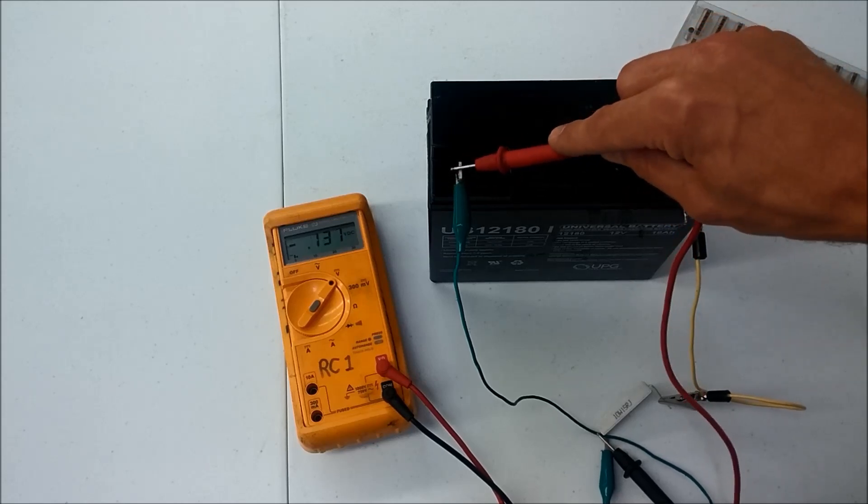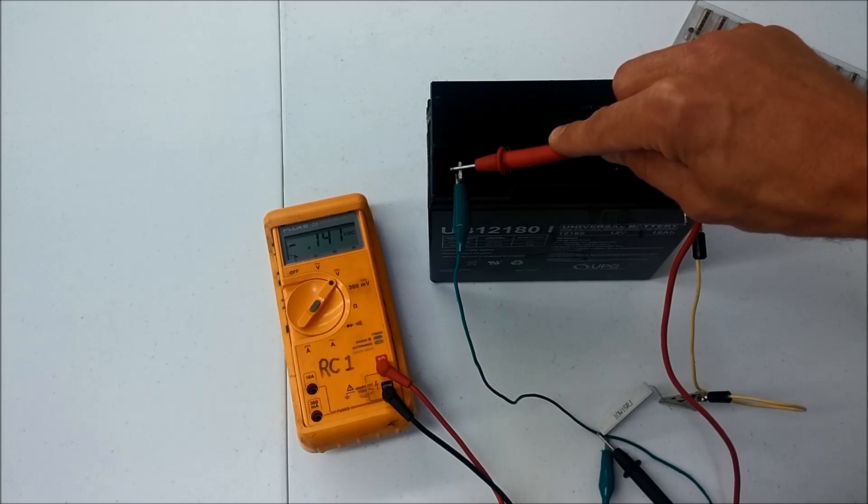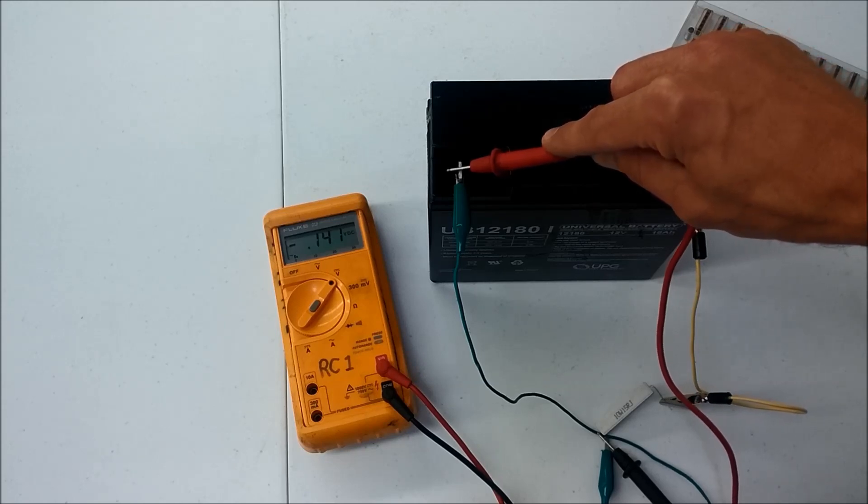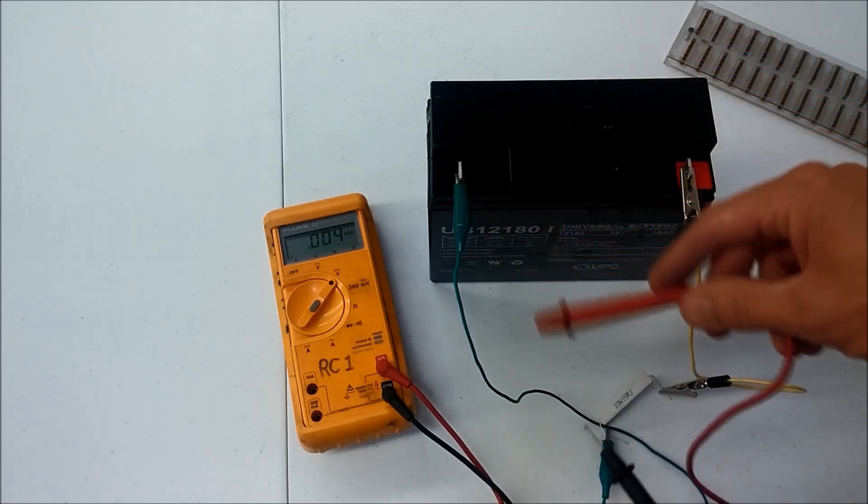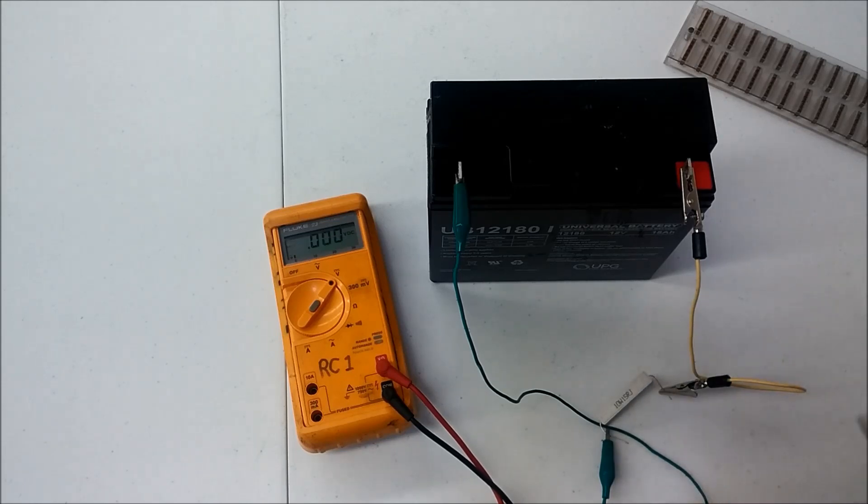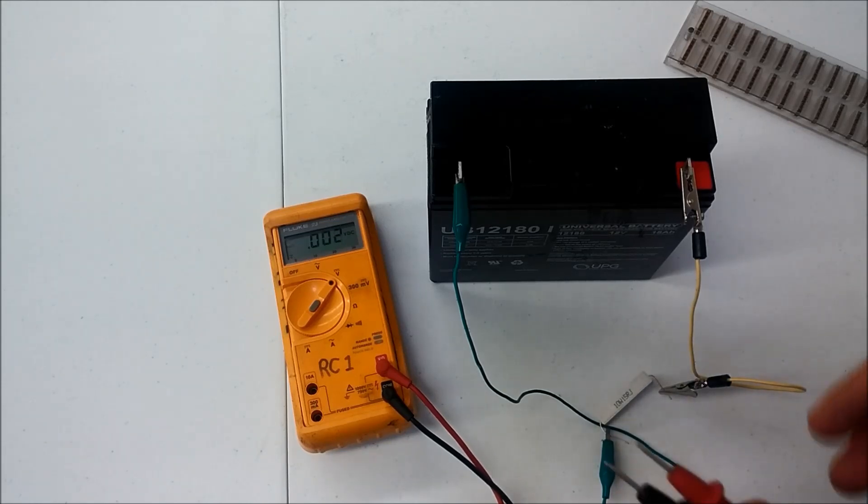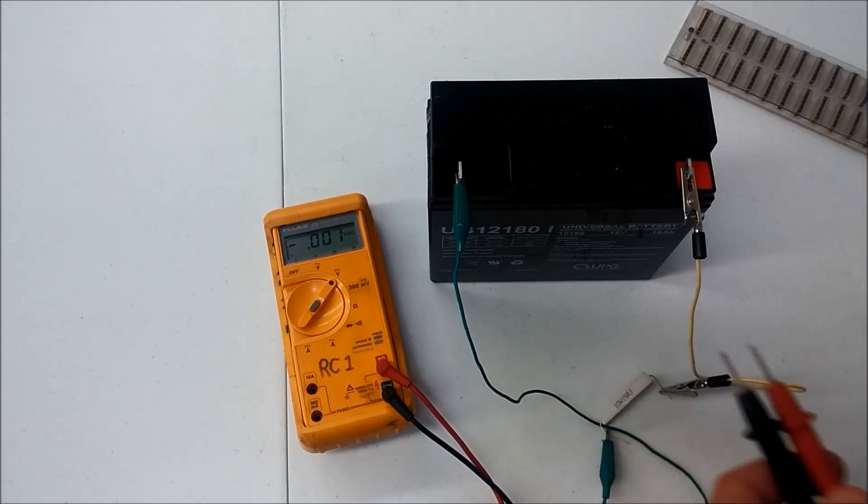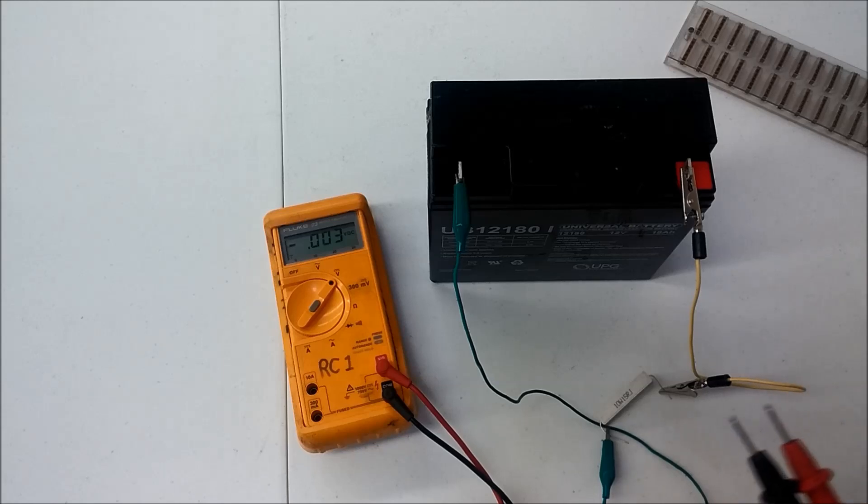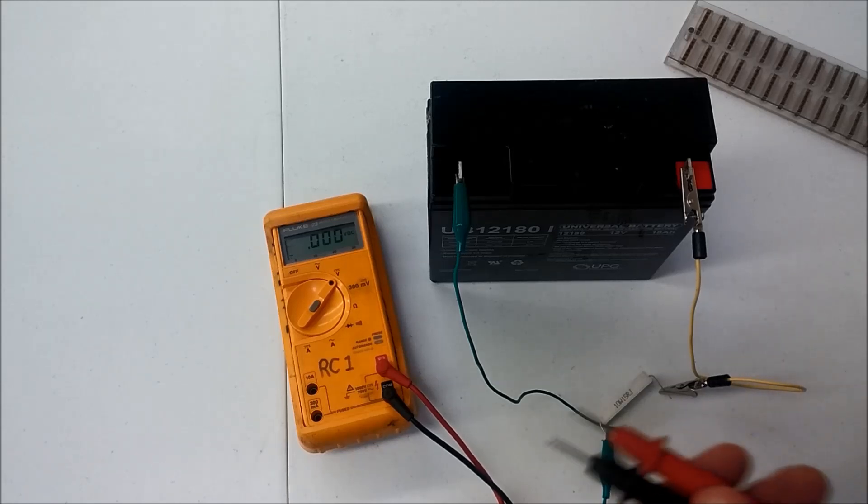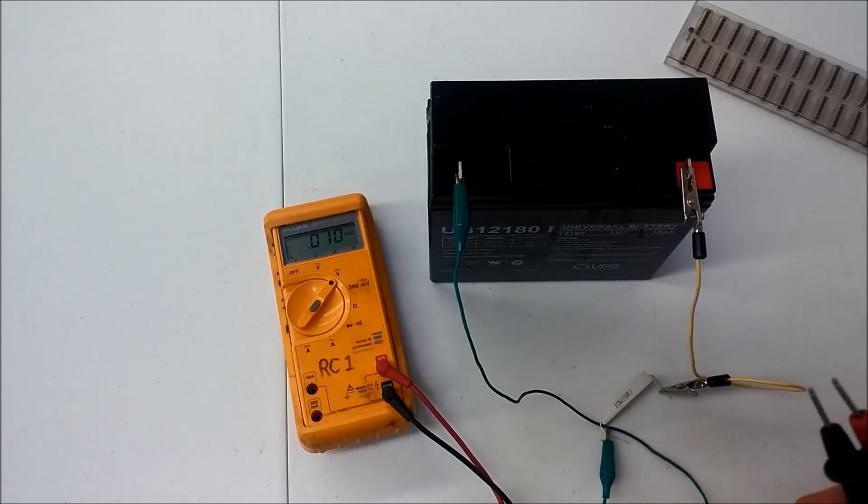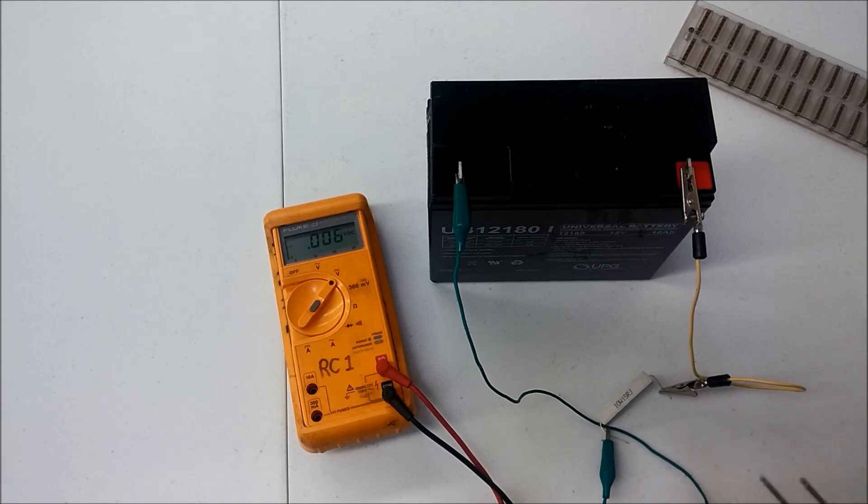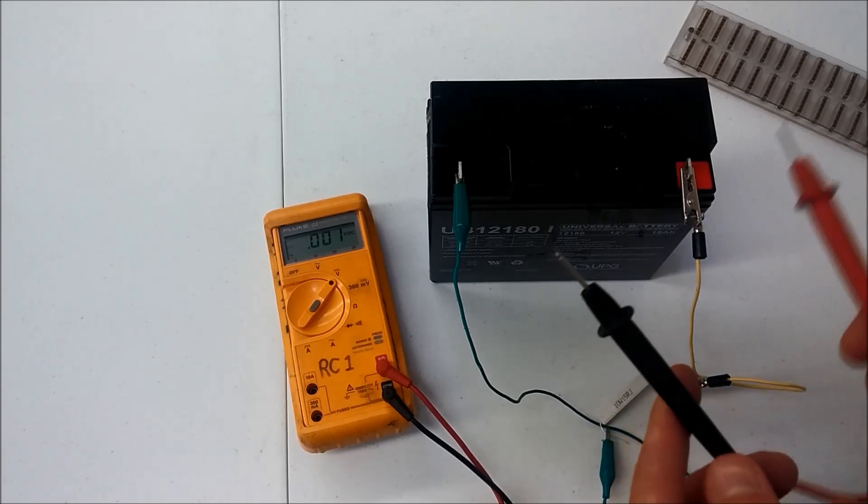Sure enough, it's close. About 0.14 volts difference from one end of the green wire to the other, so that green wire is actually causing a small voltage loss, but it's not a lot. It'd be similar to a kinked hose. If you had a garden hose and it was kinked, you'd be losing some pressure because it was kinked. But anyway, that's how you measure voltage.